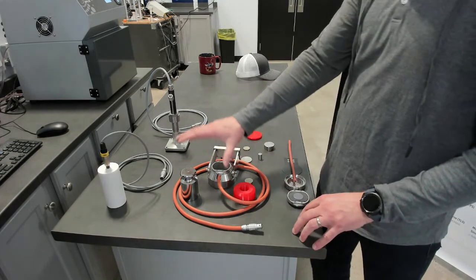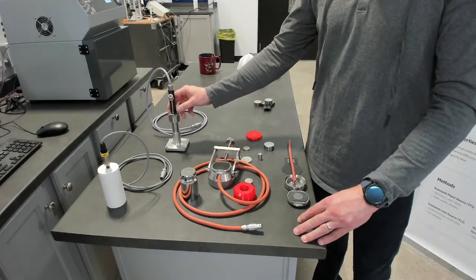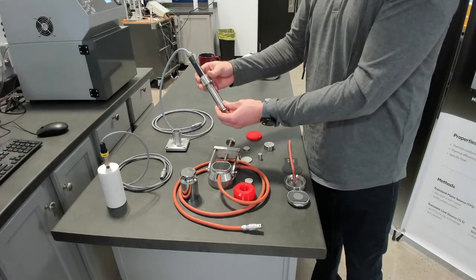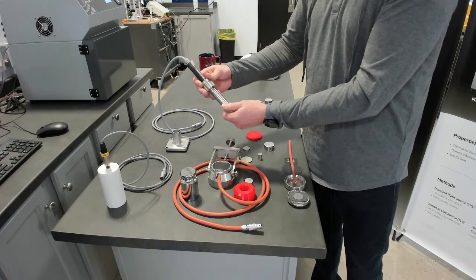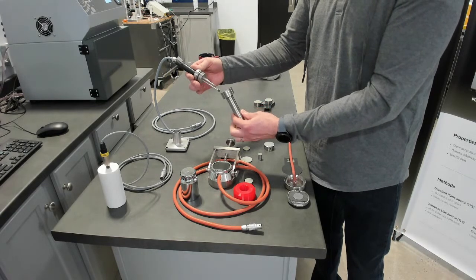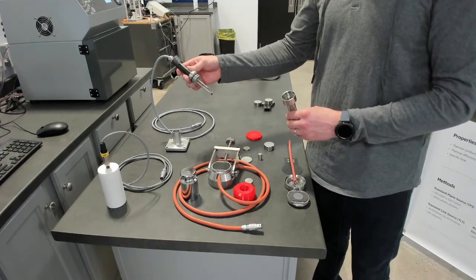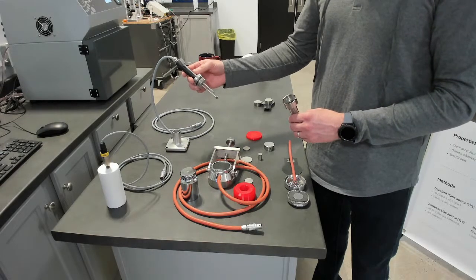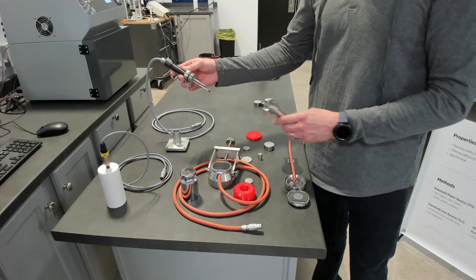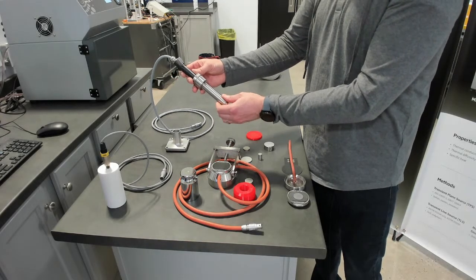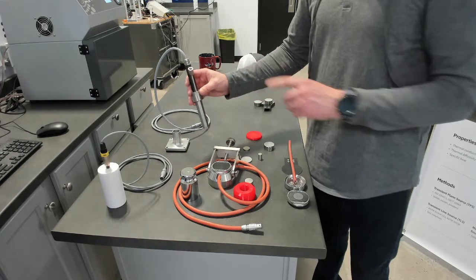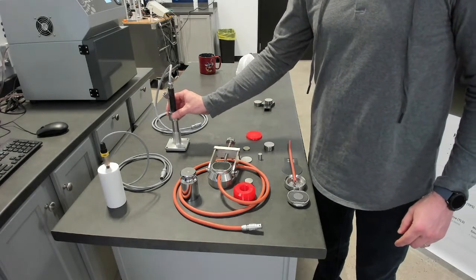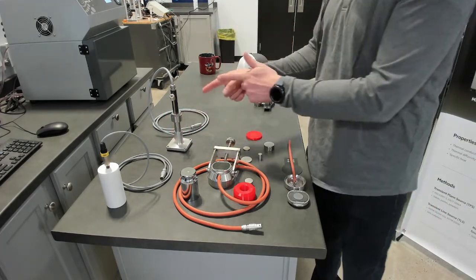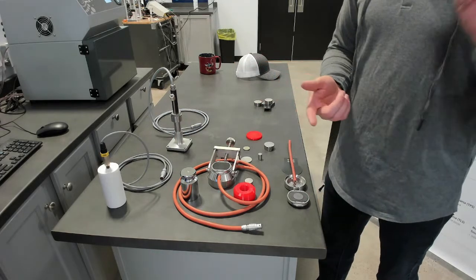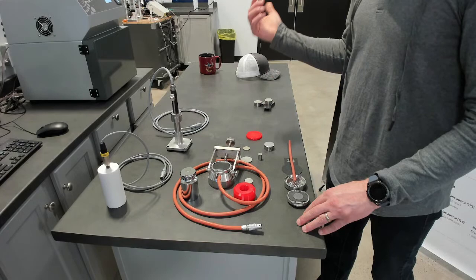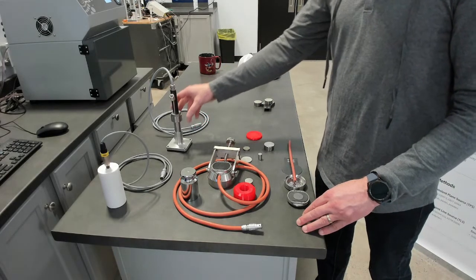So in addition to the MTPS sensor, we can offer an upgrade on the transient hot wire sensor. The major upgrade is back pressure. The sensor that's included with the MPV is ambient pressure, and this is one of our sensors we've pulled from our THWL series for measuring approaching boiling points or past boiling points. The temperature upgrade on this is up to 100 degrees, but with the ability to measure with a back pressure, you can measure approaching boiling points depending on the temperature range of your fluid. Of course, if you need higher temperature than that, we offer a 300 degree version within the MP1 series and our THWL1. So we have the ability to go up to 300 degrees, and cryogenic if your application needs.